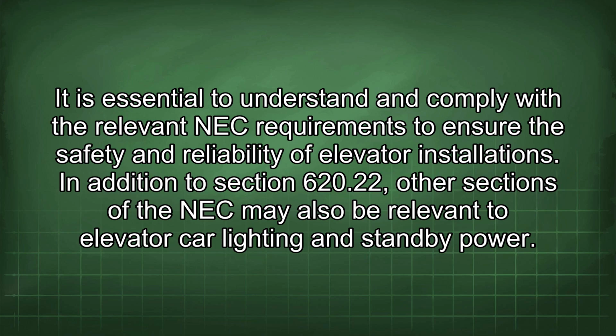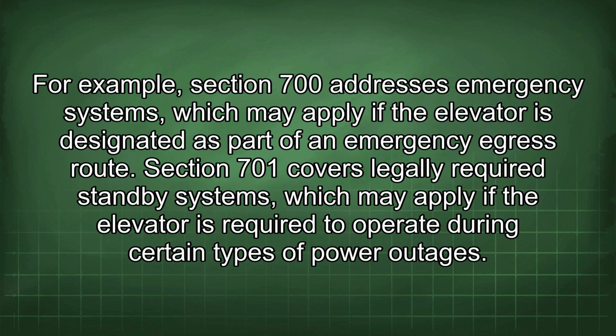In addition to Section 620.22, other sections of the NEC may also be relevant to elevator car lighting and standby power. For example, Section 700 addresses emergency systems, which may apply if the elevator is designated as part of an emergency egress route.